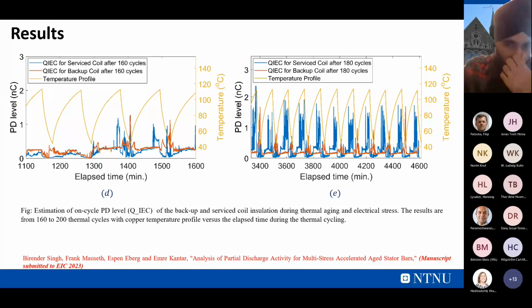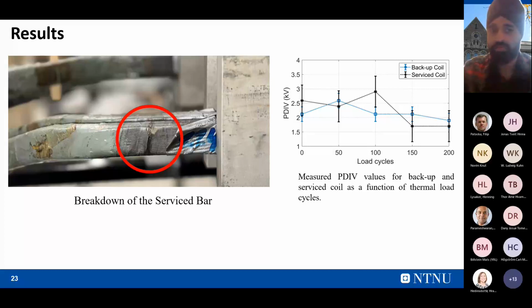And after 200 cycles, which was very clear from these observations, we conducted the experiment and found the breakdown of the serviced bar at this point. If a needle-like gap of 1 micron or 2 microns is there, then that gap will be a problem for the insulation and will ultimately break down the machine, because a crack of 1 or 2 microns inside the material will cause carbonization of that channel and ultimately lead to the breakdown of the machine.